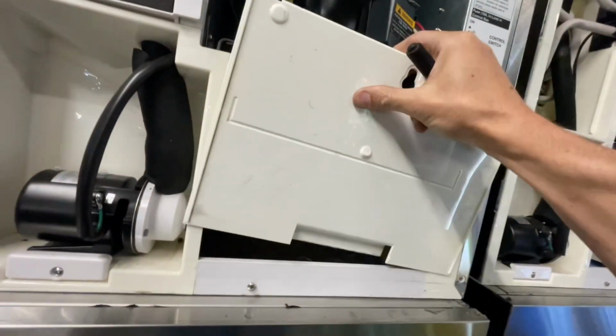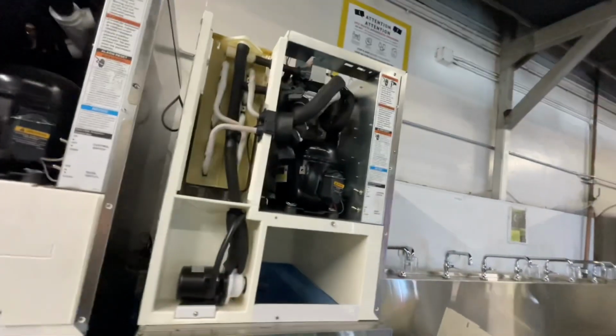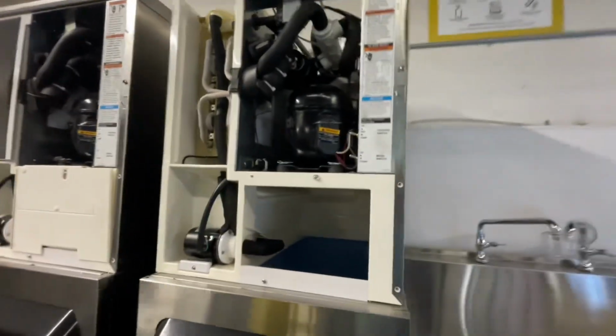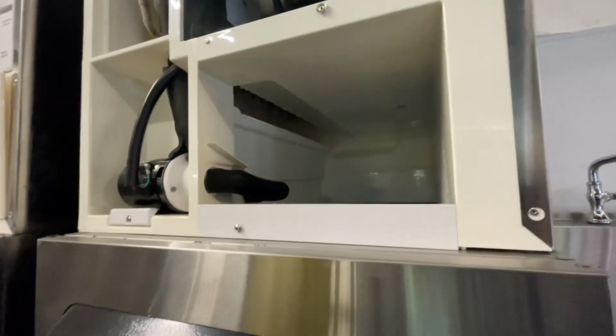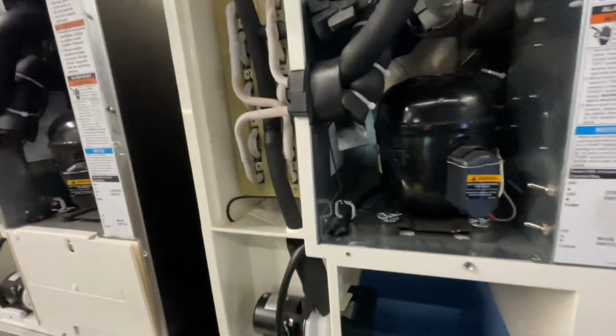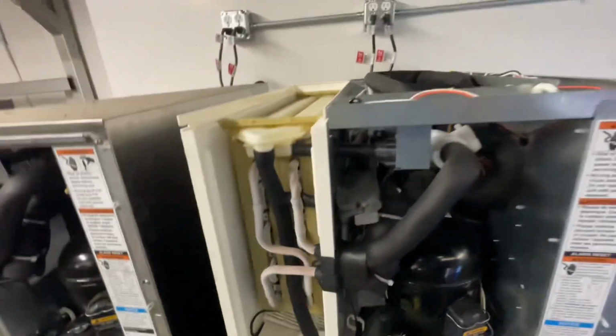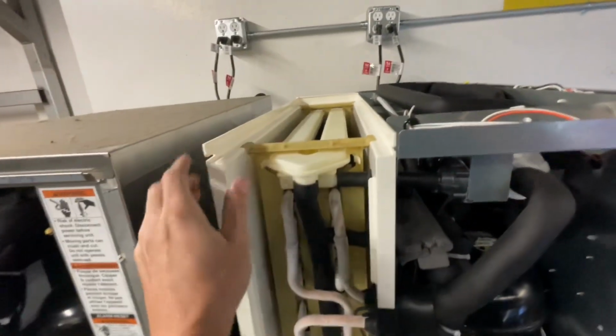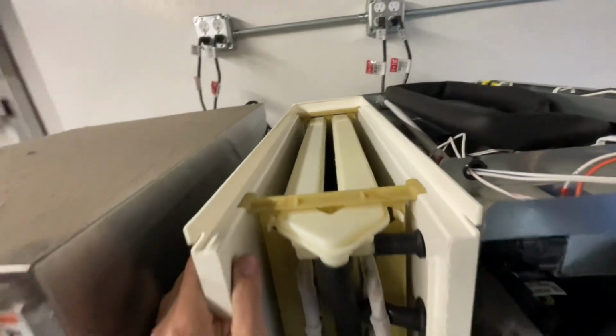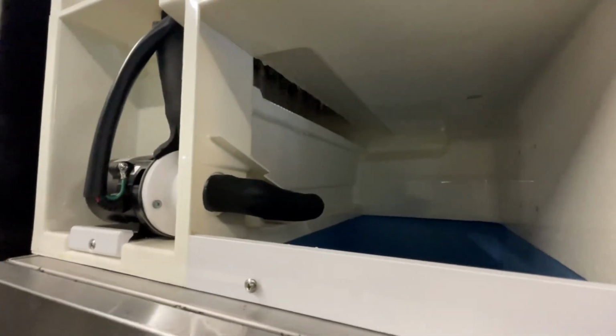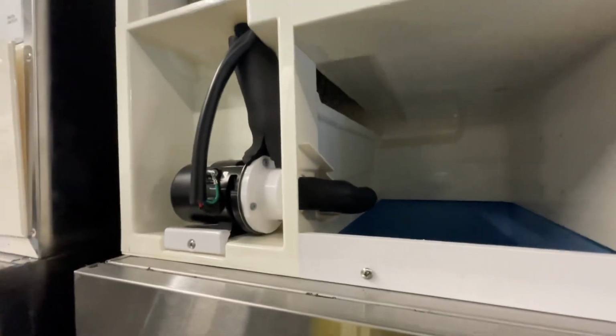I am under the assumption that this machine here probably experienced a freeze up and then shut off on our 2 beep alarm, which just means harvest time exceeded 20 minutes for 2 cycles in a row. The machine shut off. It was off for long enough for the ice to all melt and fall out of there by the time I showed up.